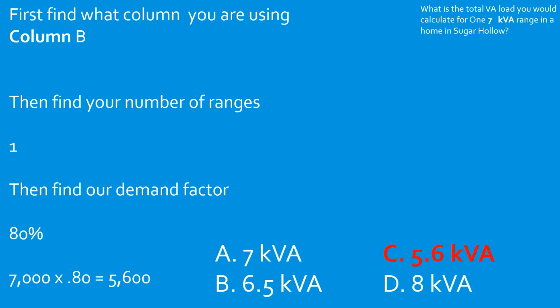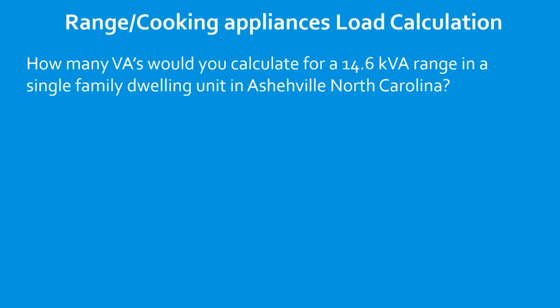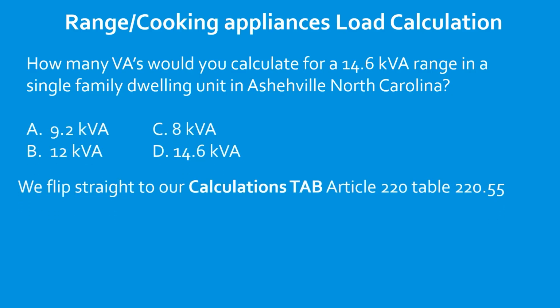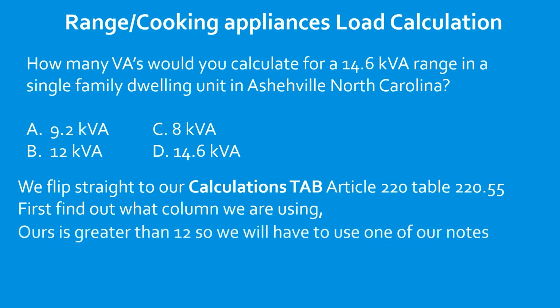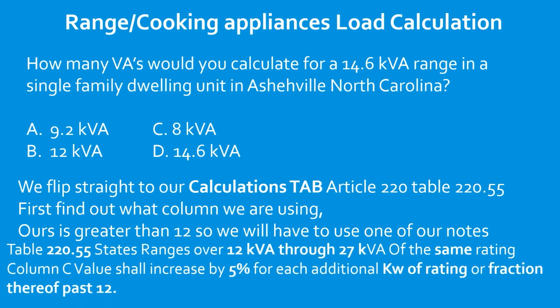Let's get to it. All right, let's get into a little more complicated type questions. How many VAs would you calculate for a 14.6 kVA range in a single family dwelling in Asheville, North Carolina? So we're going to flip straight to our Calculations tab, Article 220. We're going to find out what column we are using. So we're in Table 220.55. Well, in this case, we're going to be using one of our notes. So anytime your range goes outside of 12 kVA, you know that you're going to be using one of your notes. You're going to be either using note 1 or note 2. Well, in this case, we're going to be dealing with note 1 because we only have one range, okay?